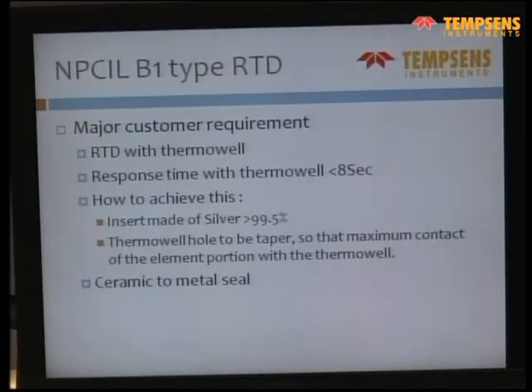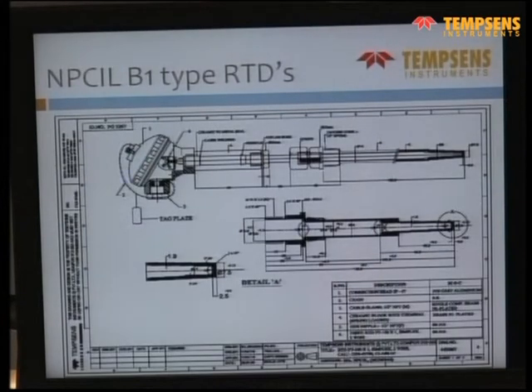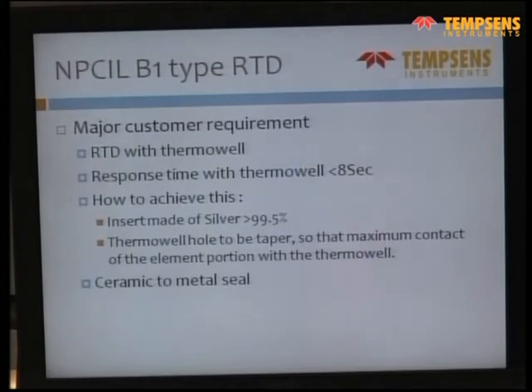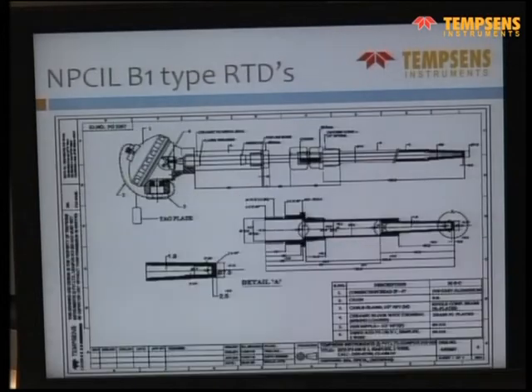There is another type of RTD for NPCIL in which the response time required is less than 8 seconds. We saw this a few slides back. Here the insert was made of silver and the thermowell was tapered so that you have the maximum contact for an RTD. And they want the life to be more than 20 years. So each RTD is with a ceramic to metal seal. It's not just general epoxy with which we are sealing the cold end.